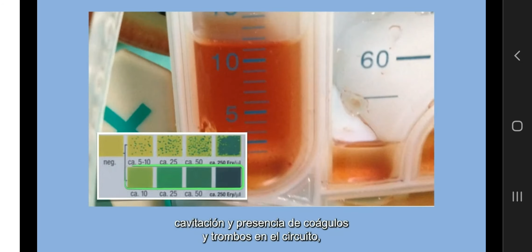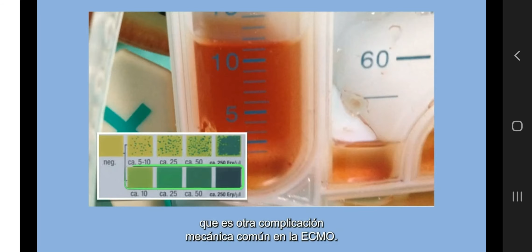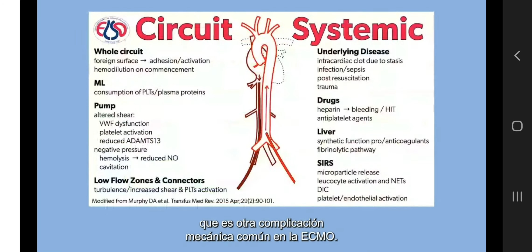Another main determinant is the shear stress associated with turbulence, cavitation, and the presence of clots and thrombi in the circuit, which is another common mechanical complication on ECMO. During the run, the interaction between the blood and the non-biological surfaces of the extracorporeal circuit, even if surfaces are completely coated, may lead to a systemic inflammatory response, triggering the adhesion, the activation, and the consumption of procoagulant and anticoagulant factors and other blood components. Moreover, the shear stress, the turbulent flow, and non-physiological pressures may additionally activate and damage blood components.